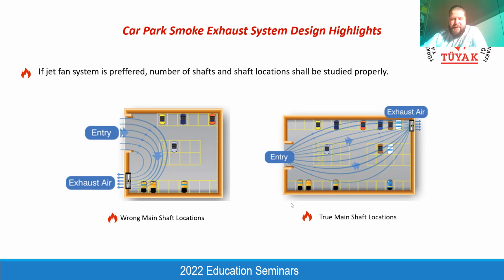You need to coordinate with the mechanical designer for the shaft locations, and you need to locate shafts as far as possible from each other, so that the fresh air can be moved by jet fans and the smoke will be sent to the exhaust shafts and extracted from the building to the outside. That's why the shaft locations shall be studied from the beginning of the project, because when you start to pour the concrete for the basement floors, to open a new shaft will be very impossible for the structural guy and also for the construction team.